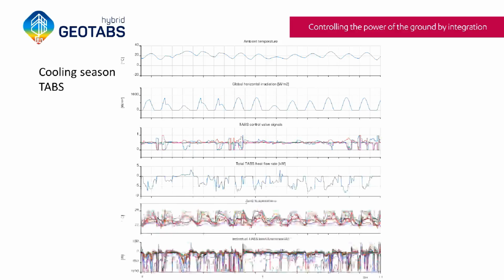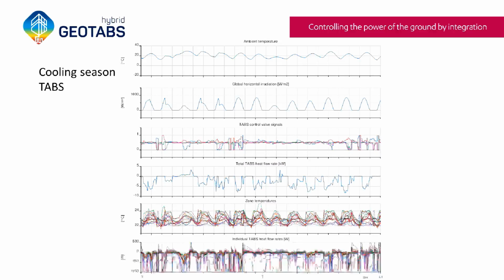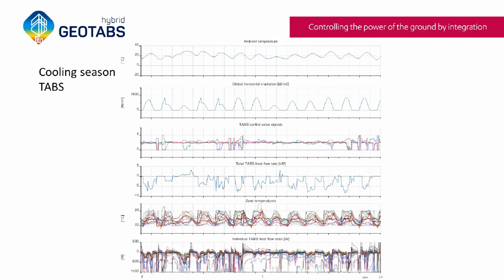One thing I want to point out here is that, for instance, you see that we have no total heat flow rate going towards the TABS. So you may say that cooling and heating are both disabled, while in fact the individual heat flow rates of these TABS are not zero. Some of them are cooling and some of them are heating, which essentially means that they're exchanging heat between them.